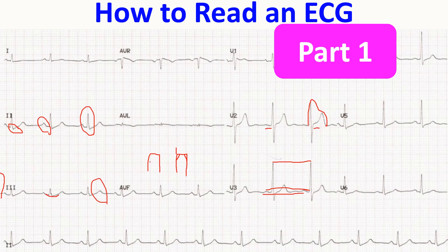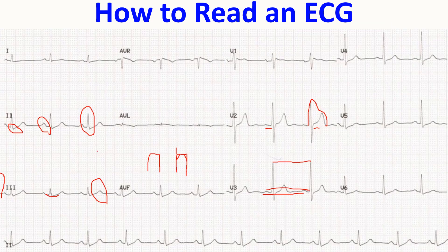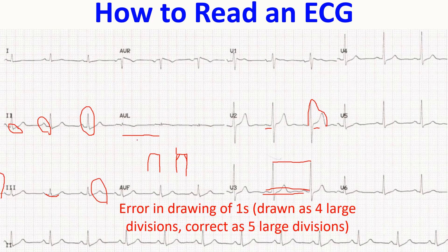This square wave corresponds to 10 millimeters per millivolt. On the horizontal axis, 5 large squares or 25 small squares correspond to 1 second, because the standard ECG paper speed is 25 millimeters per second.